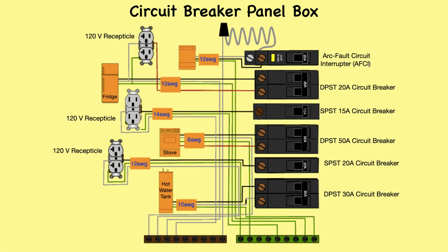The hot wire for a branch circuit is connected to the breaker by a set screw on the base. The neutral and ground wires for the circuit are connected to a bar along the side of the service panel box. The neutral and grounding bars in the panel may be separate, or in the case of older service panels, the same bar may be used for both purposes.